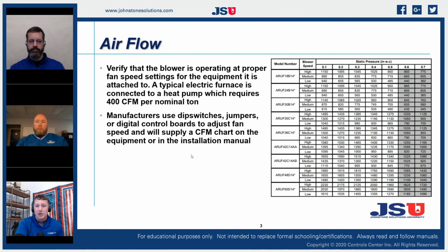This particular chart is a little over a year old. So this is when we were using a permanent split capacitor blower motor. We've now shifted over with this ARUF to an ECM constant torque. Most everyone in the industry has shifted from permanent split capacitor motors over to some type of ECM because of our federal energy requirements on our motors, right? There's a few PSC out there that are still hitting that requirement, but it's just barely, and it's a very, very small amount of them.